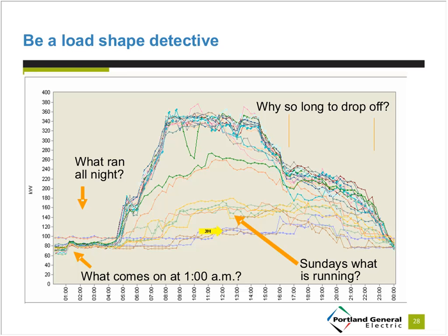And now, without looking at any data or having any knowledge of kilowatt hours or anything else, I can ask some really intelligent questions. And this is an exact example of what a manager did at the school. He asked the staff, looked over here and saw that every night at about 1 a.m., something came on and stayed on every night. No one had the answer. What was going on? What jumps on and stays on 30 days every month? Finally, someone in the IT department said, that might be us.